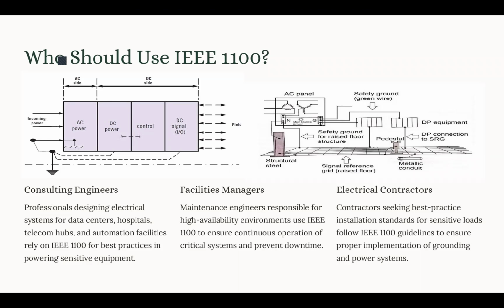So this IEEE 1100 provides those consulting engineers with engineering best practices that go beyond safety to ensure power quality, noise suppression, and system uptime. Now, the key applications are, for example, data centers. Engineers must design hybrid grounding systems to make sure of a low common mode voltage, normally less than 1 volt RMS.